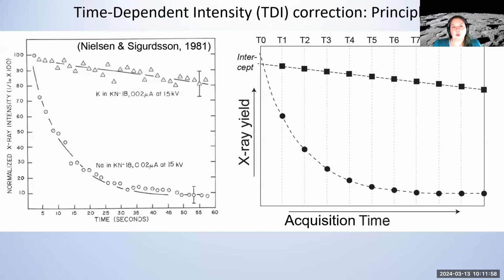While these are all good suggestions, the problem is that it impacts the precision we can achieve. Our statistics are not very good if we run very short analysis times and very low currents. We usually use the microprobe for the high spatial resolution, so having a very wide beam diameter is often counteractive to what we are looking for.